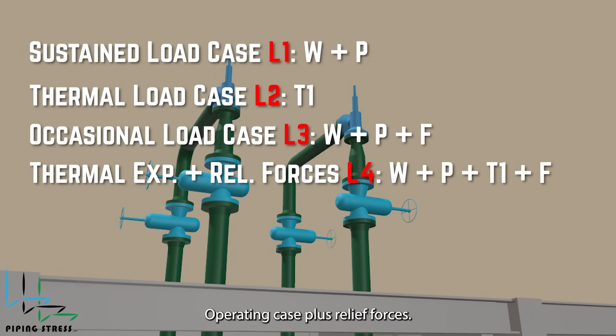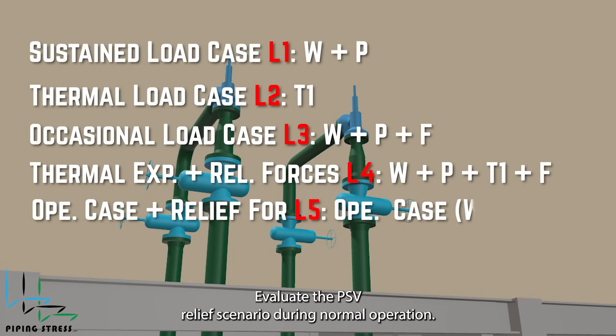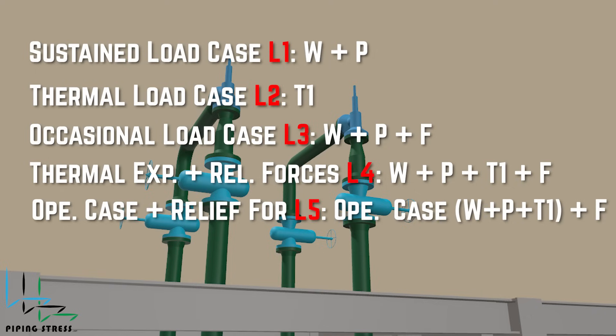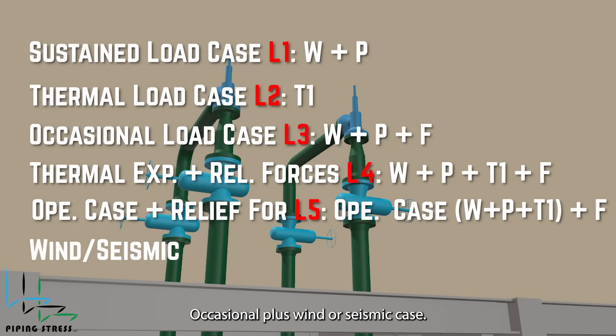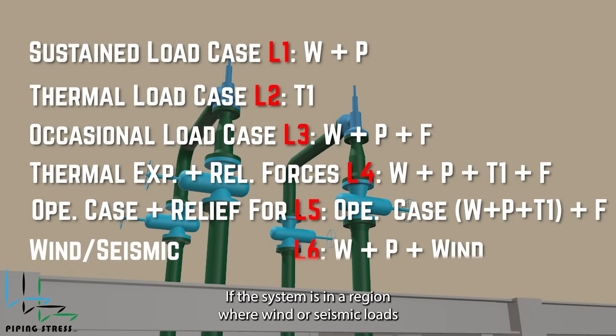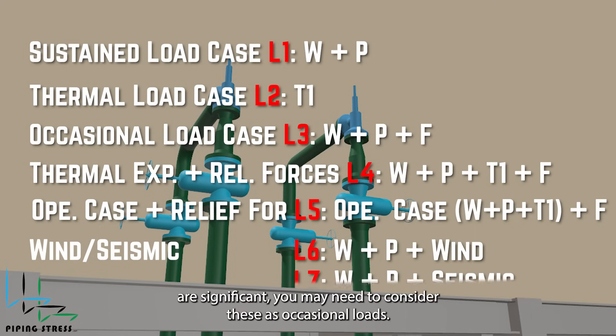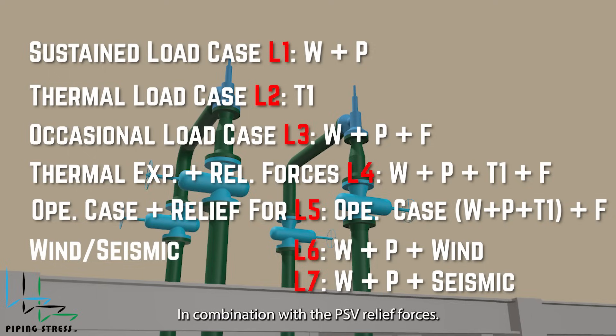Operating case plus relief forces: evaluates the PSV relief scenario during normal operation. Occasional plus wind or seismic case: if the system is in a region where wind or seismic loads are significant, you may need to consider these as occasional loads in combination with the PSV relief forces.